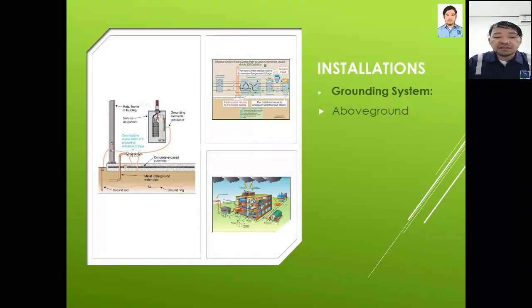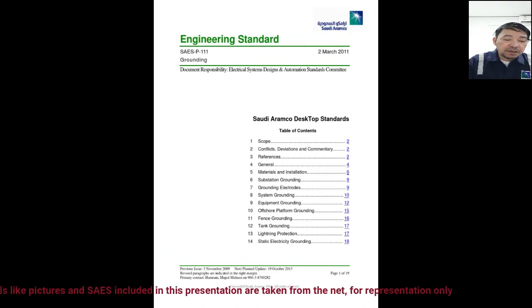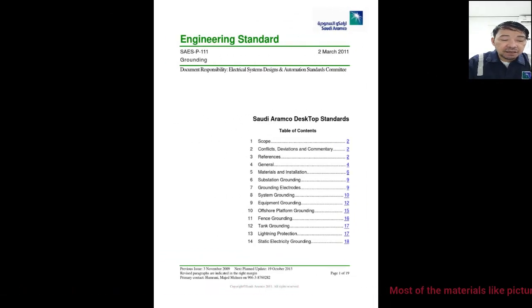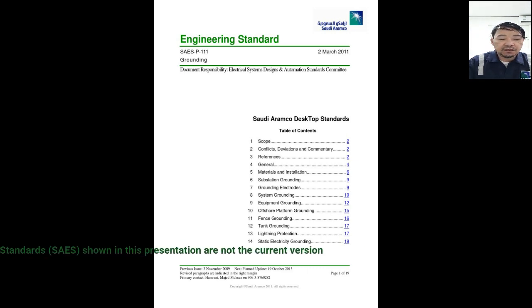Above ground grounding system connections shall be made by one of the following: A, in accordance with the National Electrical Code as supplemented by SAES-P-104. B, by thermite welding or brazing. C, to the structural steel by compression type connector bolted to bare steel. Section 5.5 of SAES-P-111: bare grounding conductor shall not be installed in metallic conduit.